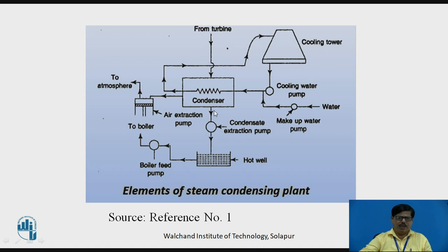The condensate extraction pump is placed between the condenser and hot well. Its function is to take the condensate at low pressure from the condenser, increase its pressure, and deliver it to the hot well. The hot well is a storage reservoir for feed water in the form of condensate. From the hot well, the boiler feed pump takes this condensate as feed water, increases its pressure to the required boiler pressure, and supplies it to the boiler. Another important element is the air extraction pump.